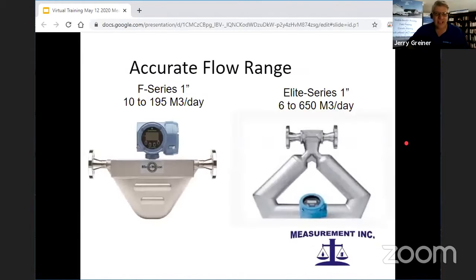We found that the accurate range in the different meters, they have different flow ranges. That was in this one, and really the accurate and the recommended range should have been from 10 cubes a day up, and we saw this inaccuracy starting about 20 cubes per day. But every meter's got an accurate flow range, and if it's not in that accurate flow range, they don't always work accurately.